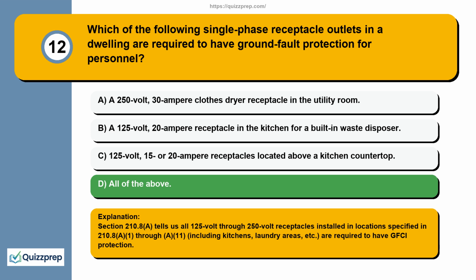Section 210.8(A) tells us all 125-volt through 250-volt receptacles installed in locations specified in 210.8(A)(1) through (A)(11), including kitchens, laundry areas, etc., are required to have GFCI protection.